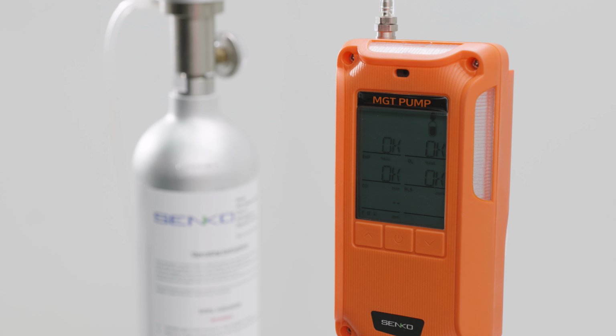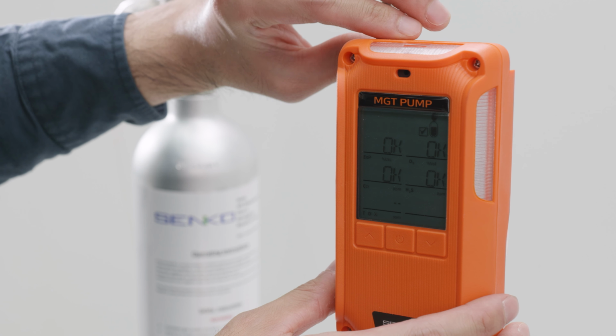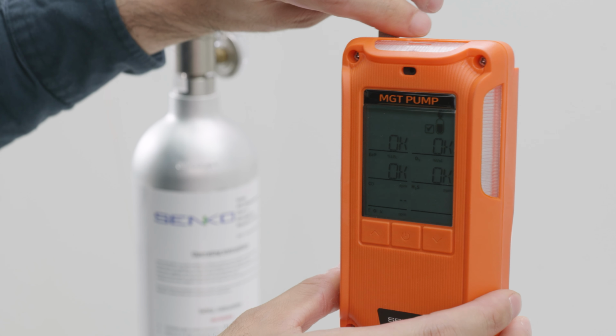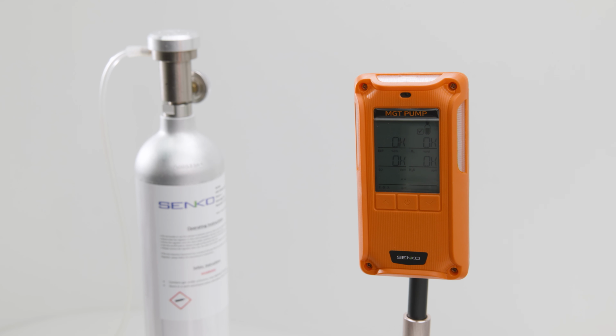If a VOC PID sensor is installed, the VOC sensor must be calibrated last, using span run as a separate step. Pump run is used to check the flow rate of the built-in pump.